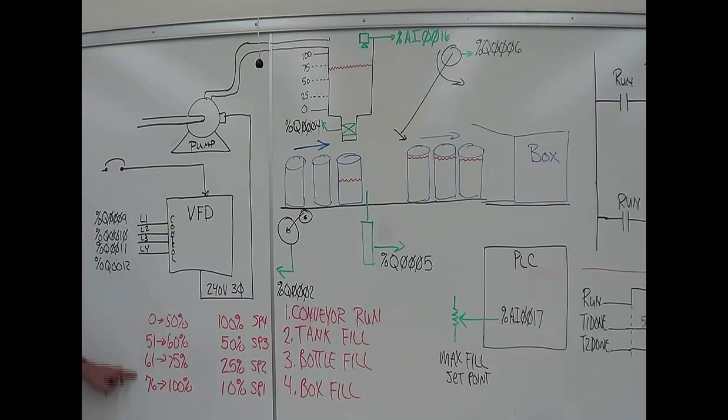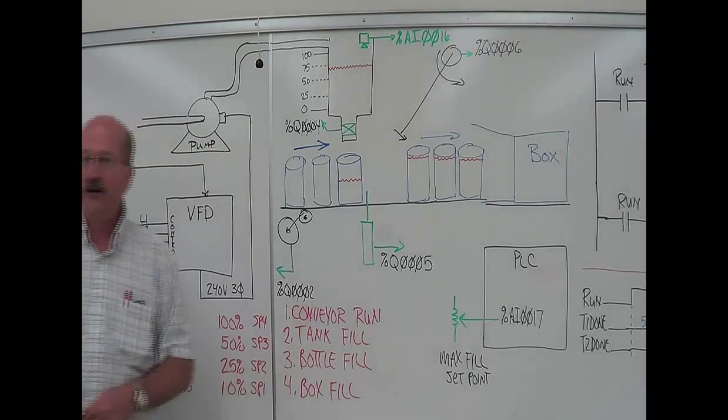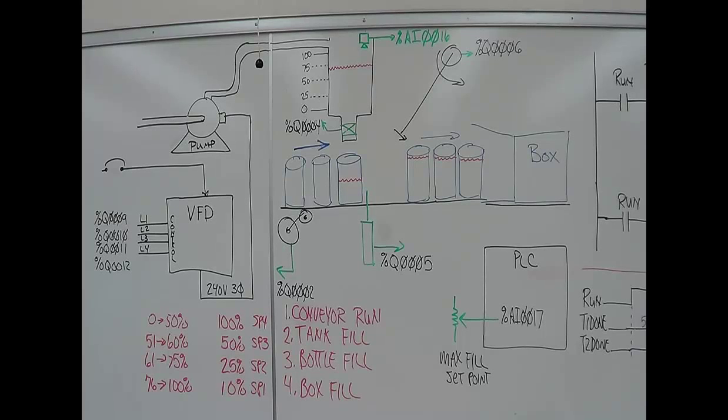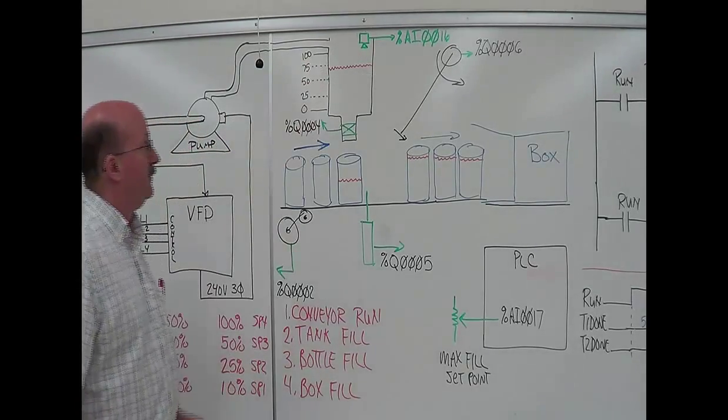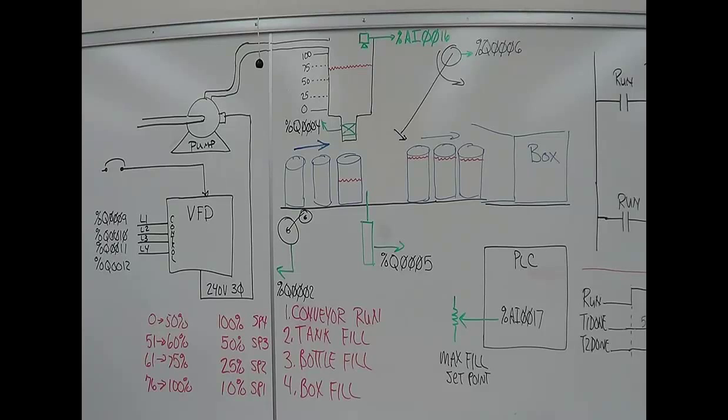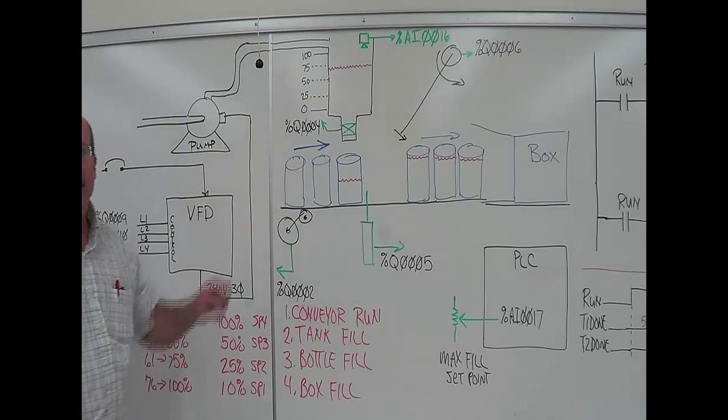Now remember, these percentages are not the absolute percentages but the percentages as modified by your set point over here on your fill point. For instance, if you set your fill point again at 50%, I don't want to go over 50% full. Well, you're multiplying whatever you're reading by that set point and adjusting the speed.